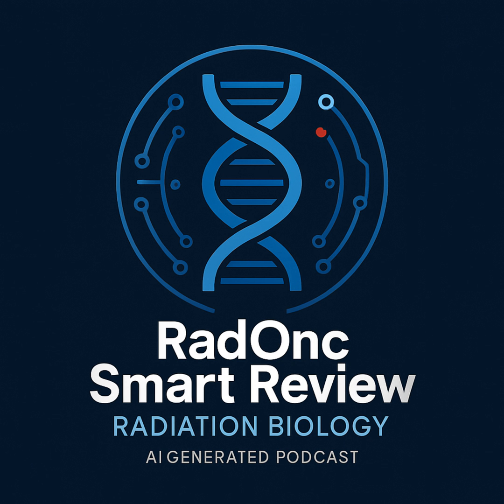And the first thing you usually notice when you compare an IMRT plan to, say, a standard 3D conformal plan. The monitor units, the MUs. They're way higher, right? Oh, definitely. You'll often see 2 to maybe even 10 times the number of monitor units compared to a simpler 3D plan for the same target dose. And why is that? It's because of all those small segments. Exactly. You're using lots of tiny fields, often blocking large portions of the beam to create those specific intensity patterns. So to deliver the same target dose, the machine just has to be on for longer. More MUs.